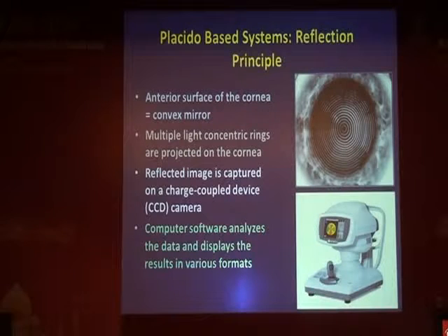Coming to the next part of the presentation, that is the Placido-based systems, and this is based on the reflection system. We know that the anterior surface of the cornea is just like a convex mirror, and with the Placido-based system, we get multiple rings on the cornea, and the reflected image is captured on a charge-coupled device in the camera, followed by computer software analysis.